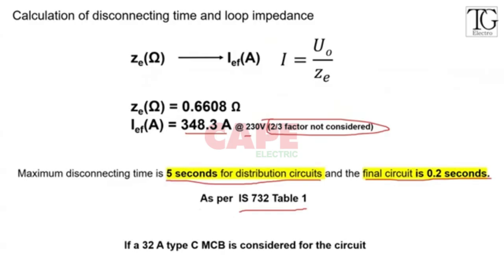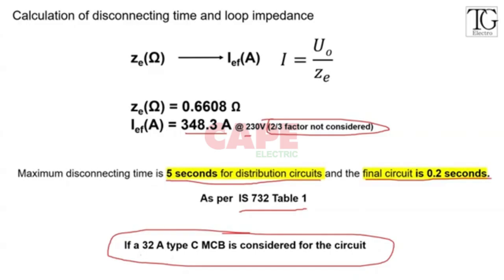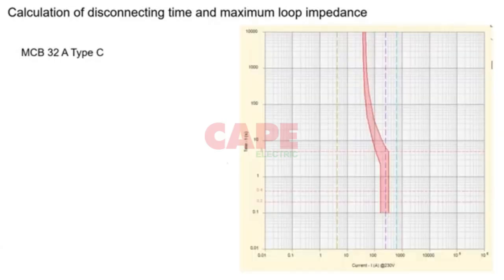So suppose you have considered an MCB. For example, for this calculation, I'm considering a 32 amp C-type MCB. I have to make sure this 32 amp C-type MCB trips at this fault current. This is what I have to check. The 32 amp C-type MCB will have a tripping characteristic like this. So ABB or Schneider, whatever it is, it is going to be like this only, because it is already defined. So the tripping curve is going to be within 5 to 10 times. So type C is 5 to 10 times.